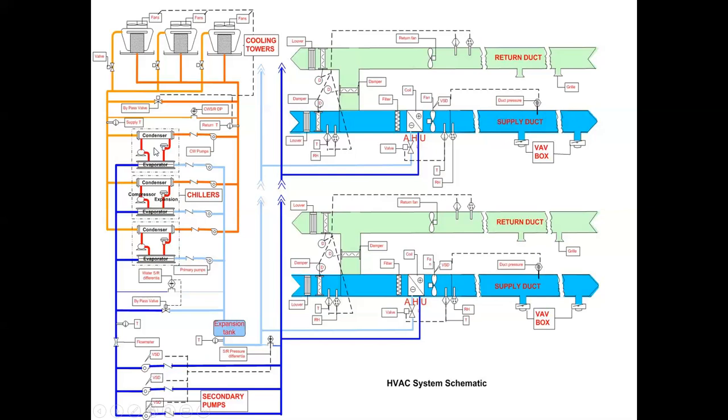That refrigerant doesn't mix with whatever it is we're making cold. In a big system like this, we're making chilled water. At Tech, it's probably about 42 degrees over in the chiller plant. 40 degrees is pretty darn cold. 42 to 44, but they make it 42 because they've got to pump it all over campus. That water goes underground from the chiller plants all the way to Derryberry, and I guess probably to the boiler house, over towards Spanky's.